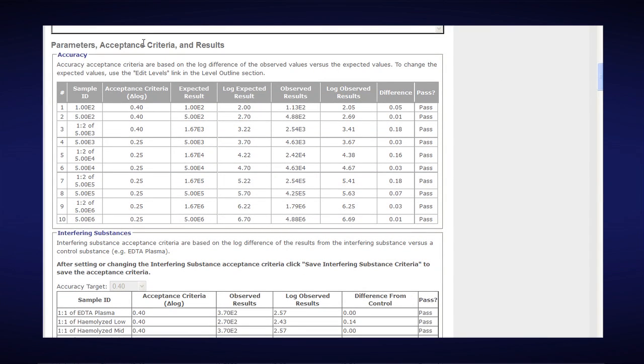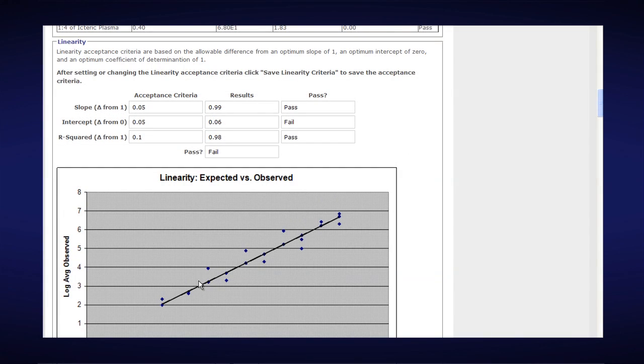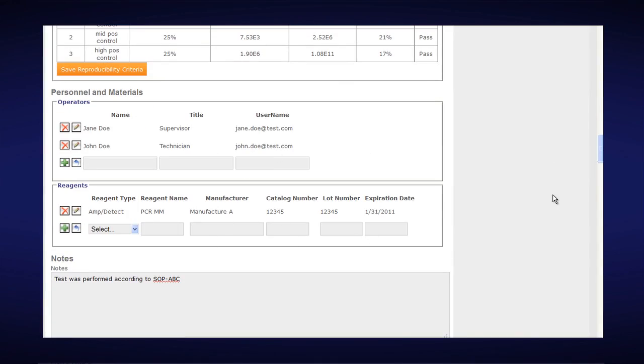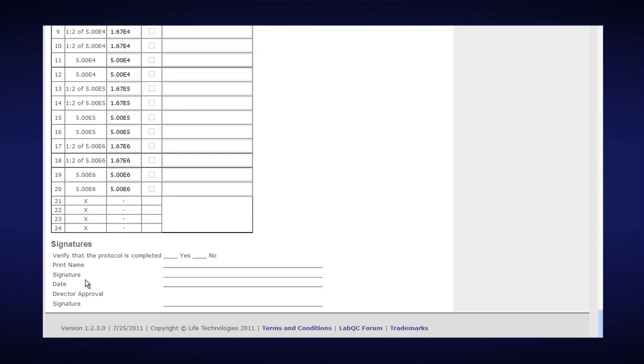Note that there is no ability to change your acceptance criteria via drop-down menu — all this data is locked in. The interfering substances study shows your accuracy target, which is your acceptance criteria of 0.4 log difference, locked in. It then shows linearity, charting the linearity as well as the rest of your data, your personnel and materials used, all your run data including yellow highlighted outliers. At the bottom of the validation report is a signature section to verify the protocol is completed: print name, signature, date, director approval, and director's signature.